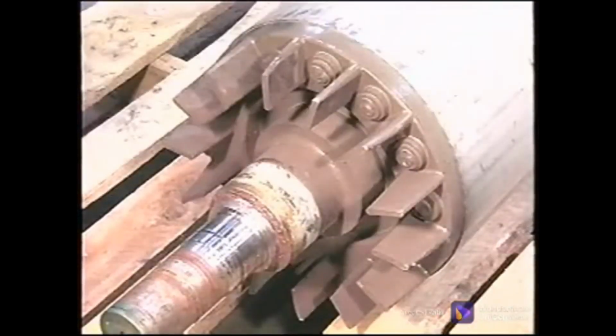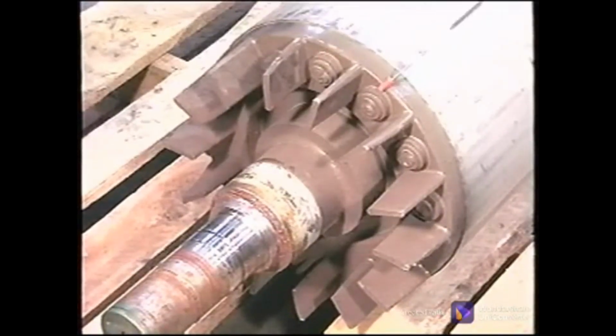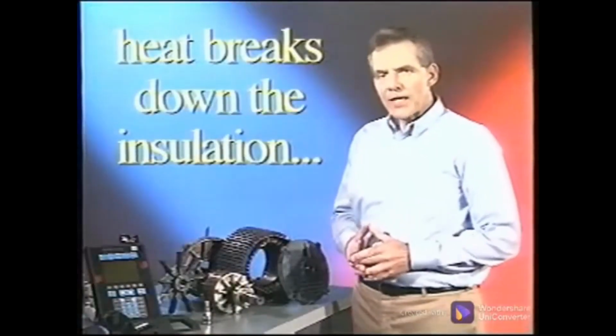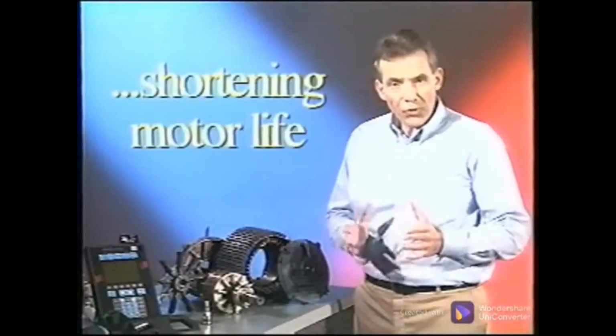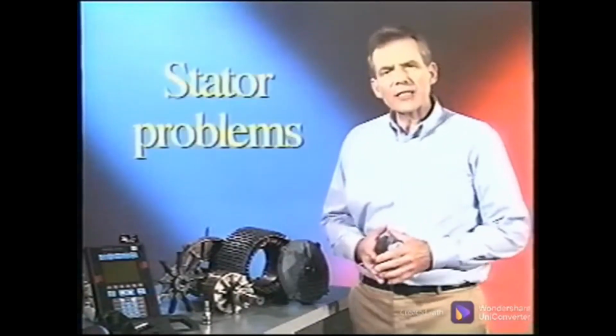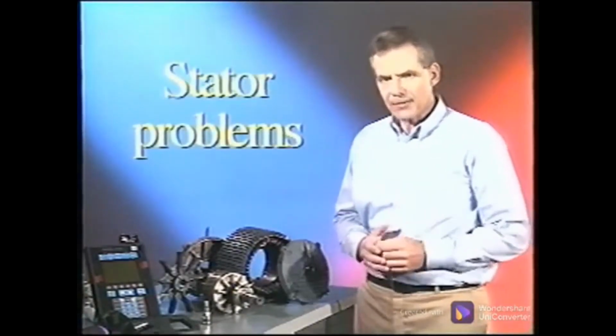A clue to a casting having large voids is there will usually be a large number of balance weights concentrated in one area. The heat breaks down the insulation on the stator windings, shortening motor life. Let's take a look at the problems that can develop in the stator.